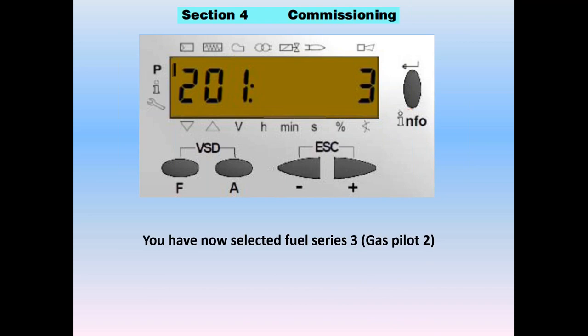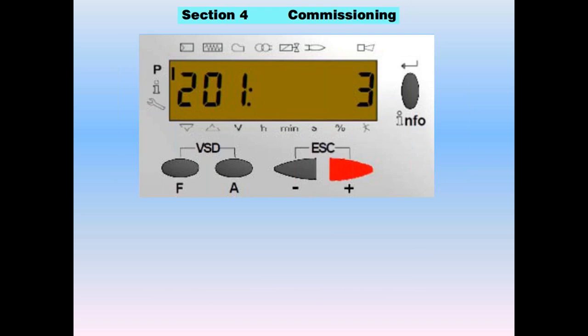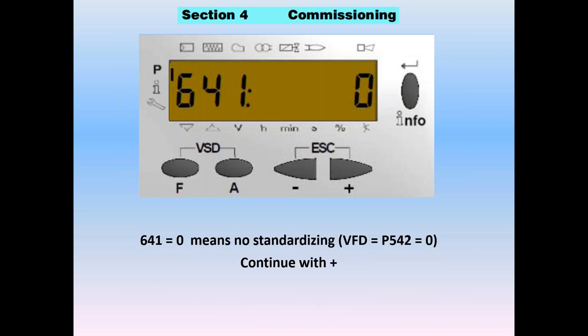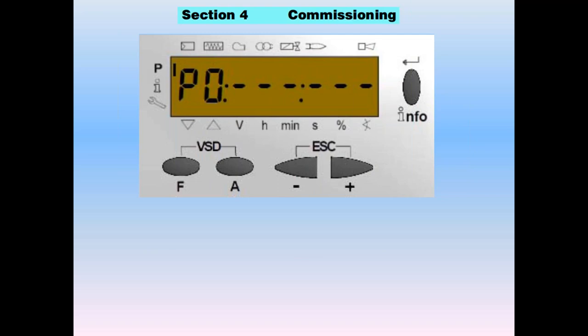Once you have that in, go plus. The first prompt will be parameter 542. A value of zero means there is no VFD or PWM — that's the case today. Continue with plus, and you're prompted for parameter 641. A value of zero means we don't need to standardize because 542 equals zero — no VFD. Continue with plus.